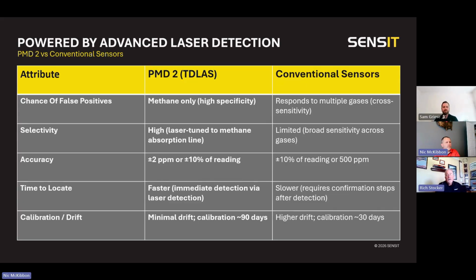Big pluses as far as the laser detection goes: a minimum amount of false positives. If you can focus again on the fact that it's methane selective, it will not be cross sensitive to anything as far as that goes. So it's not going to give us broadband sensitivity. That's the big plus on the PMD2. Very low level resolution as well as very good accuracy at a 2 ppm reading, plus or minus 10% of the read.